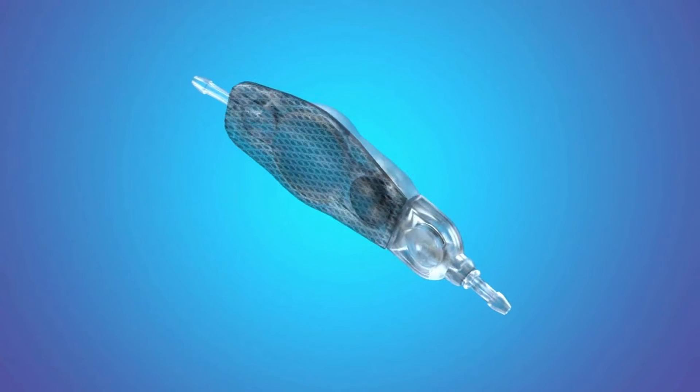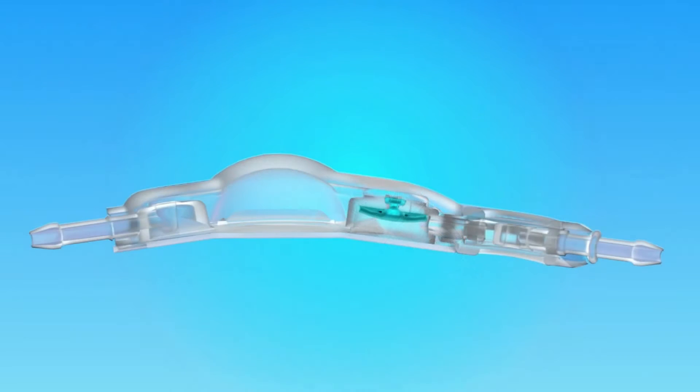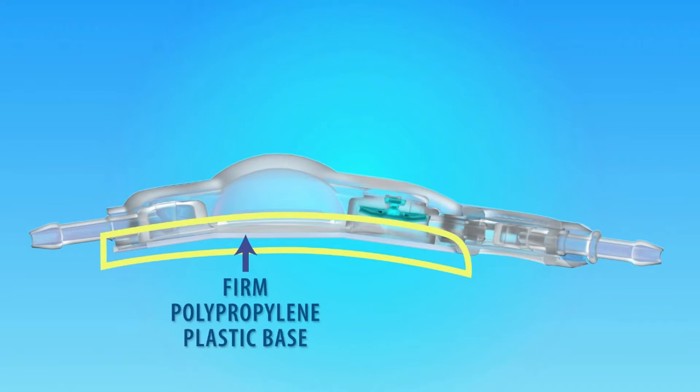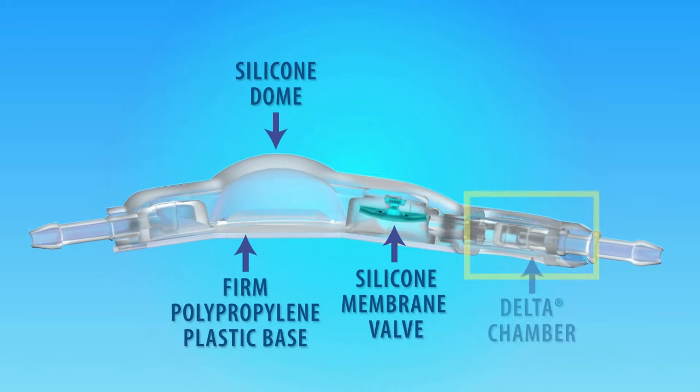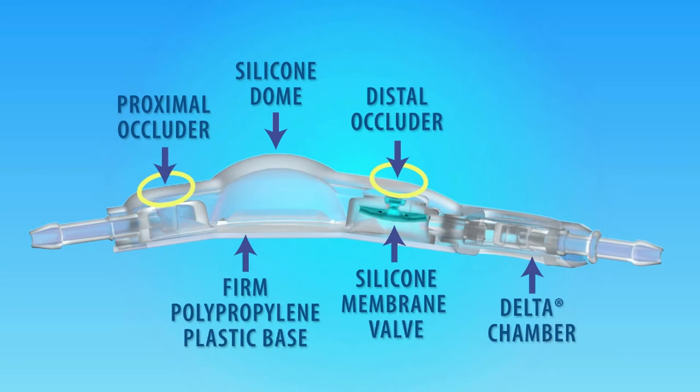The Medtronic Delta Valve consists of a firm polypropylene plastic base, a silicone dome, a silicone membrane valve, and a distal delta chamber component which provides siphon control when the patient is in an upright position. The Delta Valve also has proximal and distal occluders for selective flushing.